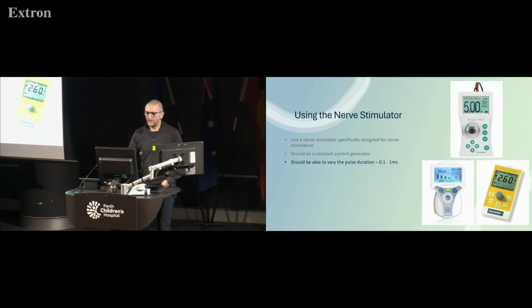You should be able to vary your pulse duration. Typically, we would start at 0.1 millisecond. Also, you should be able to vary the frequency. Generally, you would use 2 hertz. When you go to higher frequencies, it tends to be more uncomfortable for patients. It should display the current setting and the delivered current, so that you can tell that it's doing what you're asking it to do.